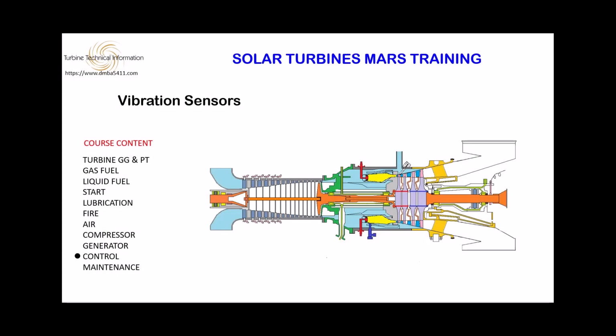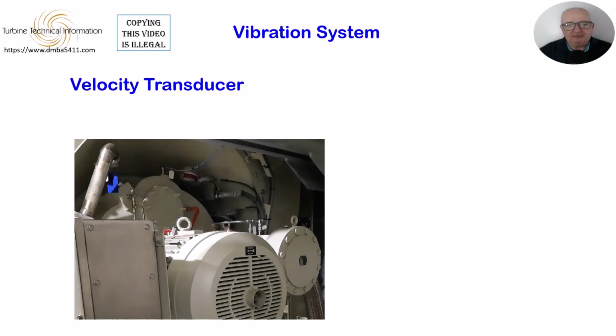Solar turbines Mars training. Vibration sensors. The Mars normally has a CEC velocity transducer mounted on top of the accessory drive gearbox, where it measures vertical low-frequency vibrations.